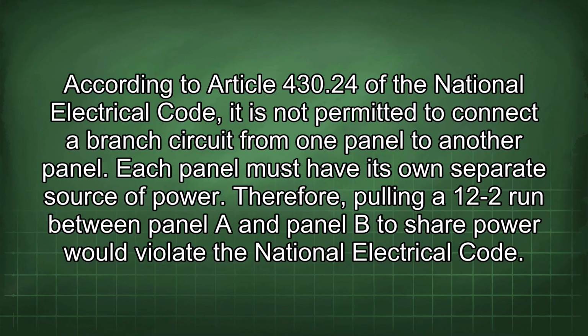According to Article 430.24 of the National Electrical Code, it is not permitted to connect a branch circuit from one panel to another panel. Each panel must have its own separate source of power. Therefore, pulling a 12-2 run between panel A and panel B to share power would violate the National Electrical Code.